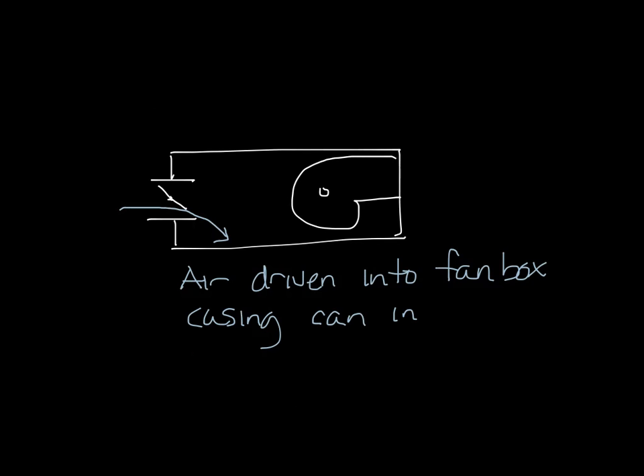Oversizing doesn't always reduce the sound of a fan box. If you go to a larger size, the damper closes down a little bit and it can drive air down into the casing and actually increase the radiated sound of the box.